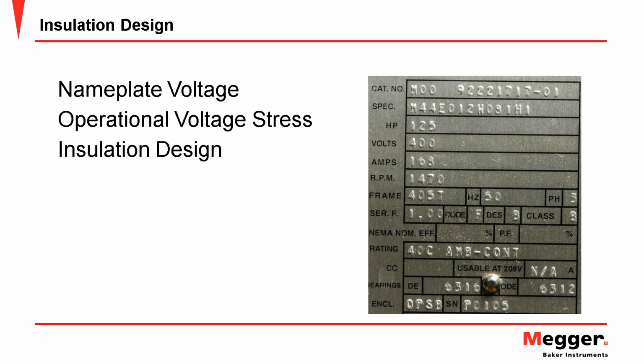A couple of things we have to keep in mind about motors and their design criteria is that there's a couple of different voltages that we're discussing here. It's not all just the same thing. Oftentimes we're very familiar with a nameplate value. On this particular nameplate I have a picture of here, the nameplate voltage is 400 volts. And that voltage represents the operational voltage. So the voltage, in this case for a three-phase AC motor, that we would apply to make the motor run, to produce torque, to produce appropriate magnetic fields and have the right current draw so that it produces the correct amount of horsepower or kW at a specific speed to drive our load properly. That's what that voltage is about.